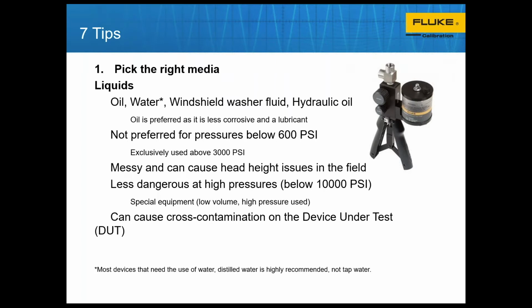They're typically a little bit more difficult to control, and the lower you go, they have a tendency to not work very well on the low side of things. But they do have a great capability of getting some very, very high pressures. The actual media that gets used can be oil, windshield washer fluid, hydraulic oil, water in some cases. Oil is preferred as it's less corrosive and it acts as a lubricant. But there are some concerns or some issues.